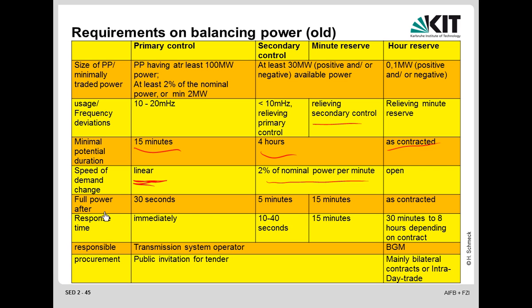And so the full power has to be there after 30 seconds, 5 minutes, or 15 minutes. And the response time for primary control is immediate. As soon as you have a deviation in frequency, they have to respond. First of all, in the beginning, it's only a marginal response. It's proportional to the deviation. But if the deviation gets larger, they must be able to provide the full contracted power, 100%, within 30 seconds.